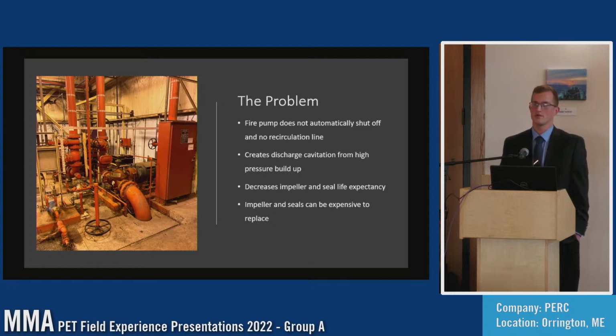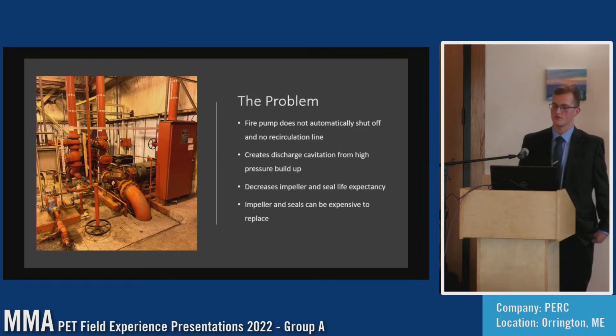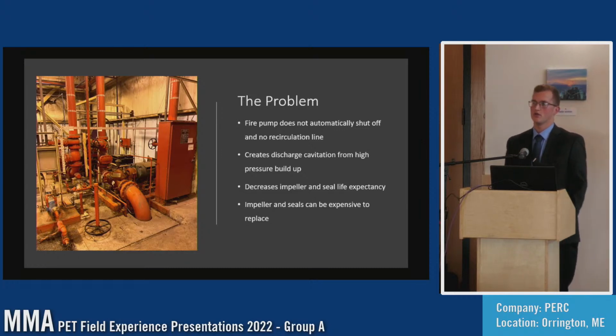The other pump is a diesel, which is a backup for the electrical pump in case there is some sort of failure. The biggest problem with this pump is that once it turns on, it does not turn off automatically. This means that somebody can open up a fire hose, the pump will turn on, water will be spraying out, and then they can close it and the pump is just sitting there cavitating.